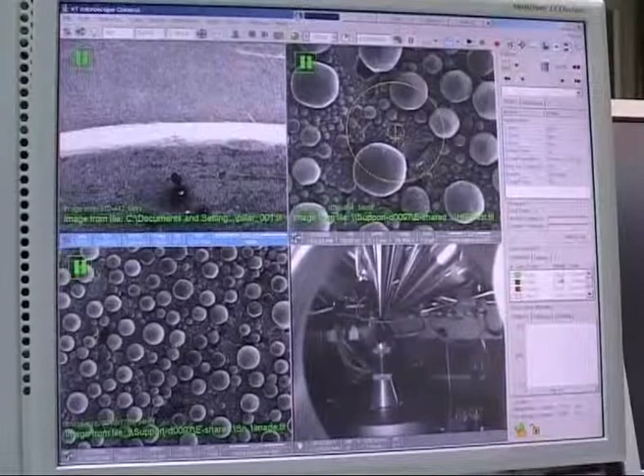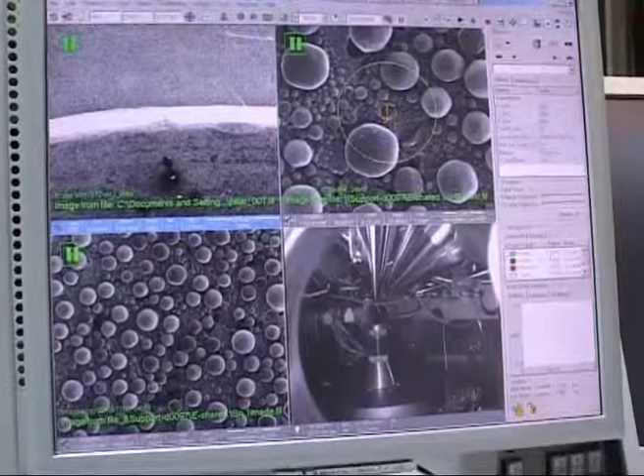Whenever we irradiate something, we can immediately look in the electron beam image at how we have sculpted the ion beam pattern over here. These are the various controls for the precursor gases: platinum, tungsten, as I said, xenon fluoride enhanced etch, then carbon deposition, and then this is again insulator enhanced etch. This one is for iodine enhanced etch, and this one is for insulator enhanced etch, that is xenon fluoride, is here. So these are all controls for the 5 precursor gases, and with the help of these controls, we first heat these gases up, and then the flow is opened, and then the ion beam is incident, and that cracks the precursor gases, and this is how focused ion beam fabrication works.